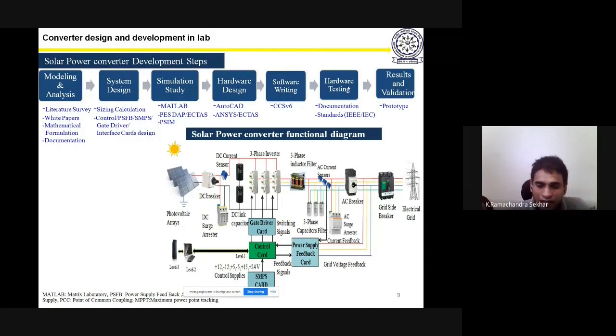So that particular feature we call LVRT, it's a low voltage ride through requirement. What that means is, for example, any fault comes at the power system side, so the demand of current is more. If you could not supply that much current, the voltage at that particular node will come down because of the lack of reactive power. So immediately there will be a dip in the voltage across the PCC. PCC means point of common coupling, where we integrate with the grid, like I shown here, the breaker. AC breaker, you can think of it as the point of common coupling.